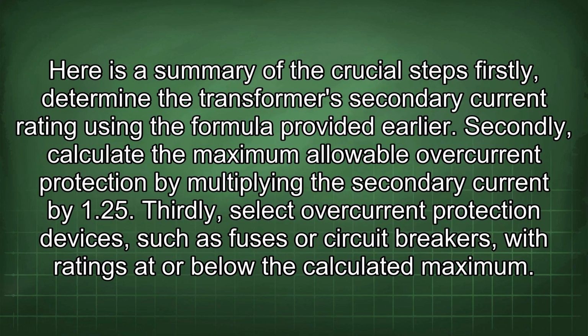Here is a summary of the crucial steps. Firstly, determine the transformer's secondary current rating using the formula provided earlier. Secondly, calculate the maximum allowable overcurrent protection by multiplying the secondary current by 1.25. Thirdly, select overcurrent protection devices, such as fuses or circuit breakers, with ratings that are below the calculated maximum.